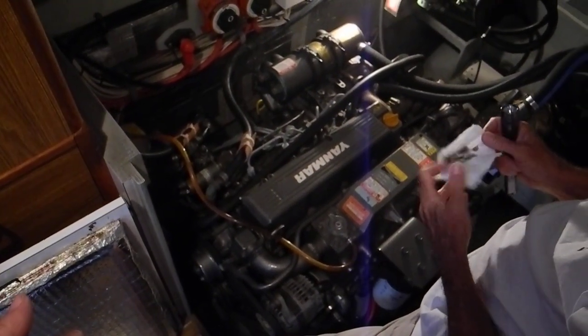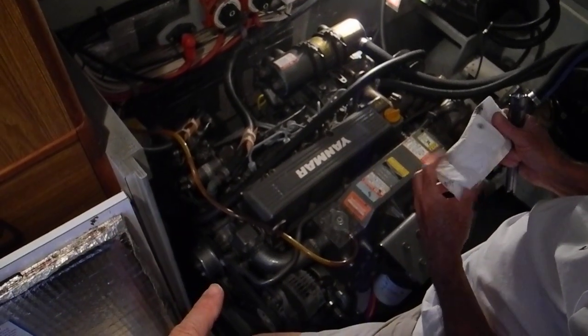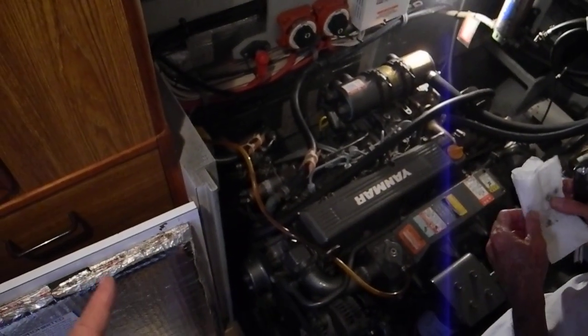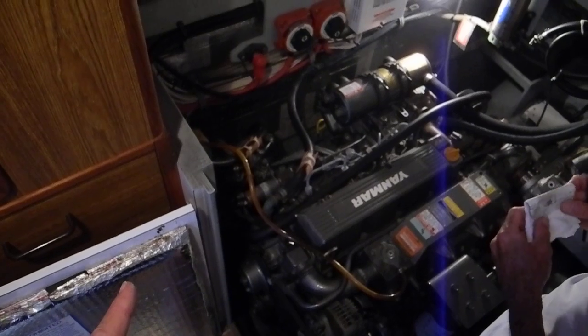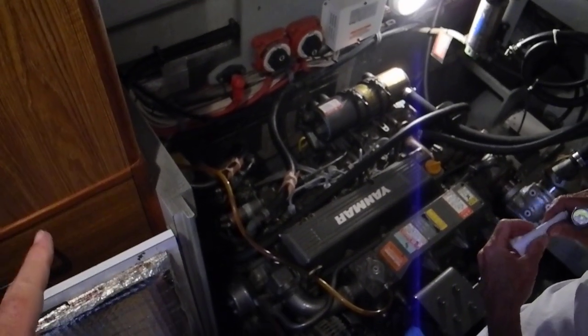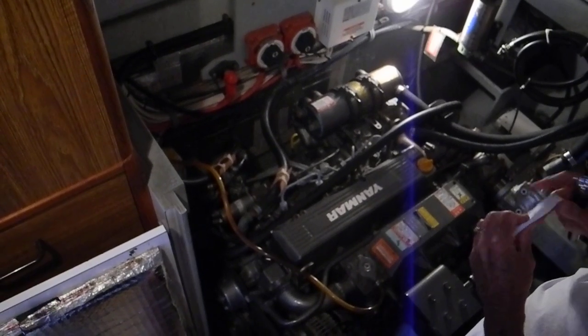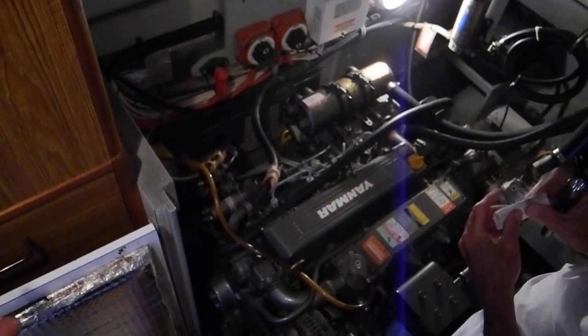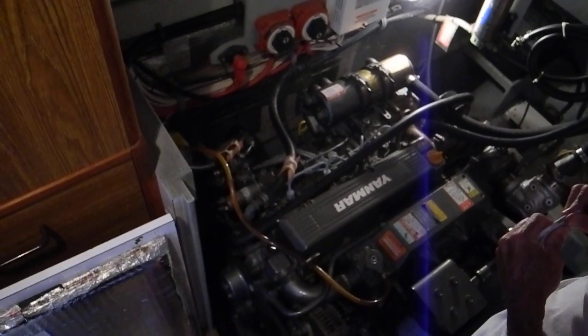Okay, but it's good to know. But with the Yanmars, if you turn the key off, the red kill button won't work. So you have to turn the key to on position, press the red kill button, and then turn it off again. Or if you forget that, then you can come down here and just do it by hand. Got it.